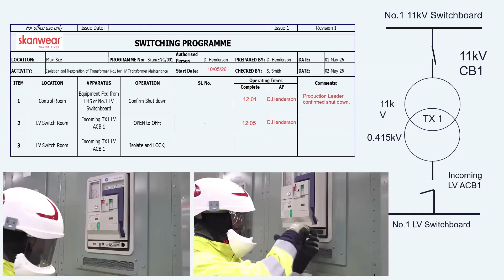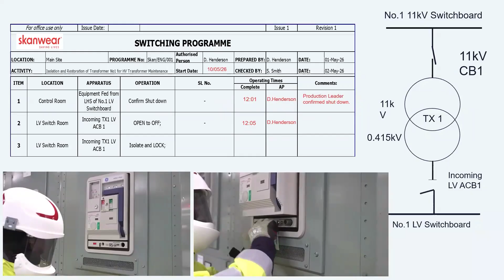The next step, I'm still in the LV switch room. And then the apparatus says the incoming TX1, LV ACB1, it's the same one that I've just operated, isolate and lock. So opening the breaker, there's not a sufficient air gap there to achieve safety from the system and prevent re-energization. So to isolate it, isolation requires a suitable air gap to prevent re-energization, and then we need it to be suitably maintained. So this is where I'll apply my lock and my tag.